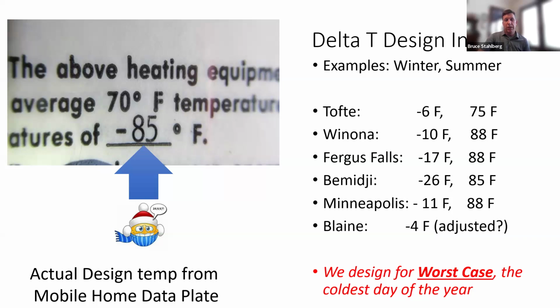Over on the left, the sentence says the above heating equipment will keep the home at an average temperature of 70 degrees inside, at an exterior temperature of 85 below. Now you think that could be a typo. That comes from a mobile home, and I've never been able to get an answer why we have 85 below design temperature, but it does seem to me that the furnace is going to be oversized if you're designing to 85 below. I like to say I lived in Crookston in the 70s and I still didn't see 85 below.